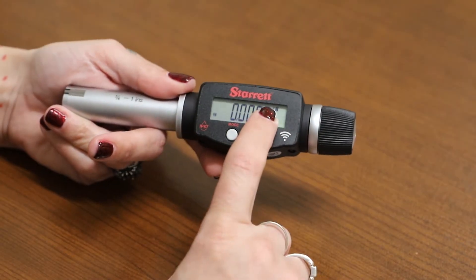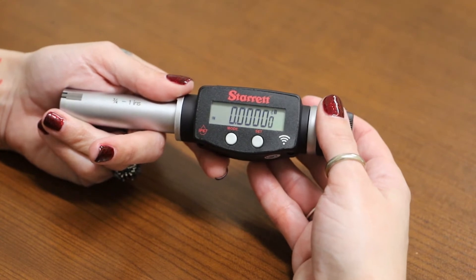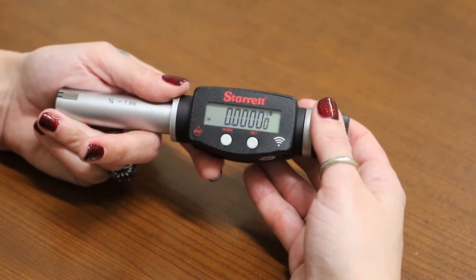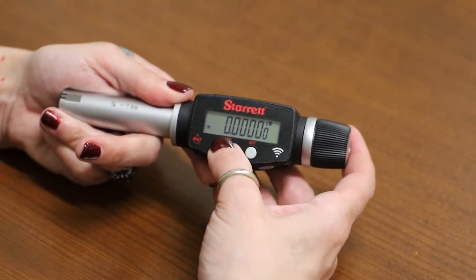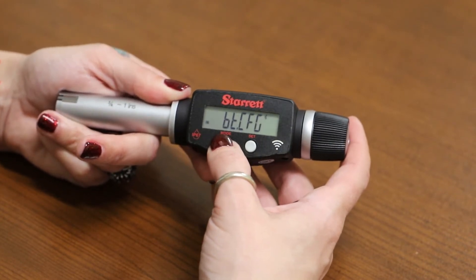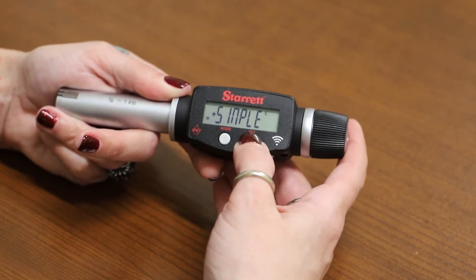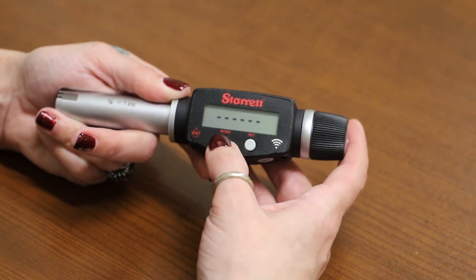Now that you have your Bluetooth on, we will pair the tool to your Datasure program. To do that, go into the second menu by clicking and holding the mode button until you see 'unit.' Let go, then click it three times to get into the Bluetooth configuration menu. Click set once to accept, then look for the pair option and click mode to pair.